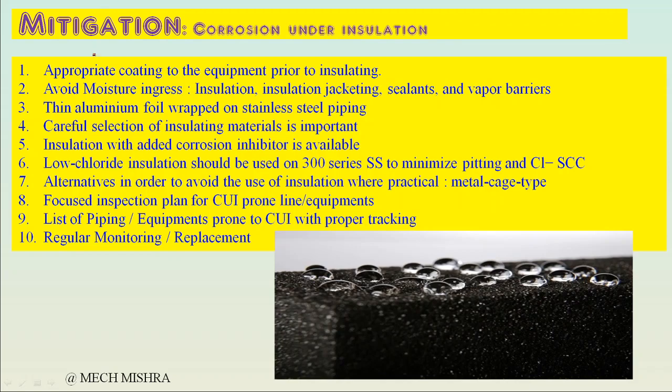First is appropriate coating to the equipment prior to insulating. We have to apply proper coating, whether it's carbon steel or stainless steel, so that it will work as a second line of defense. Then avoid moisture ingress. We have to do all the things to avoid moisture ingress, like using proper insulation, insulation jacketing, sealants and vapor barriers.